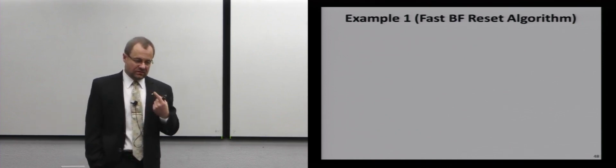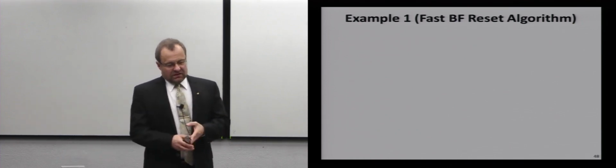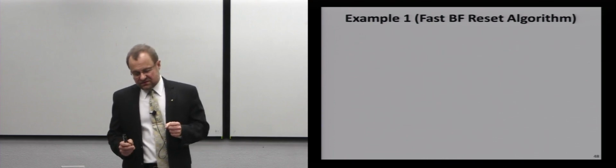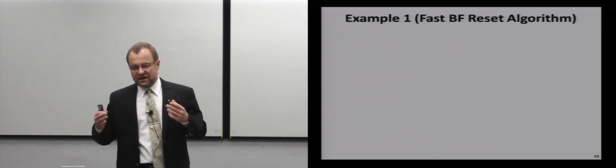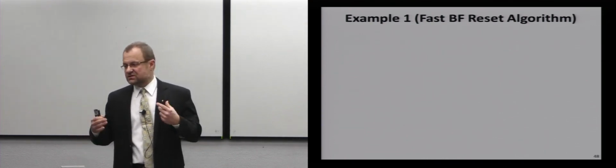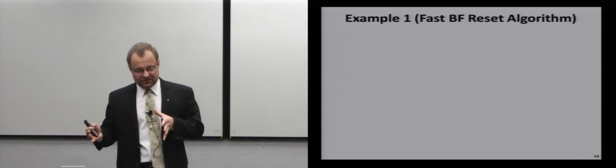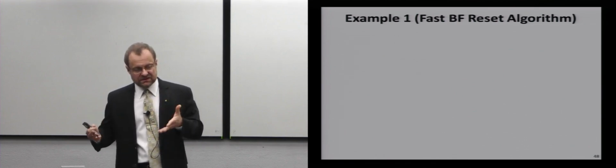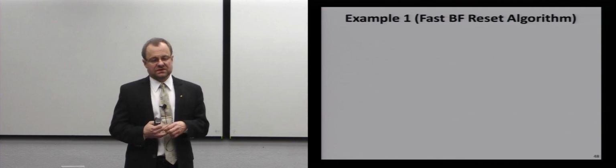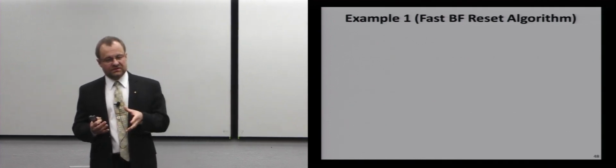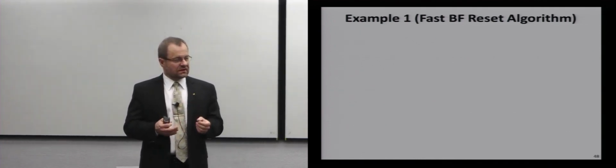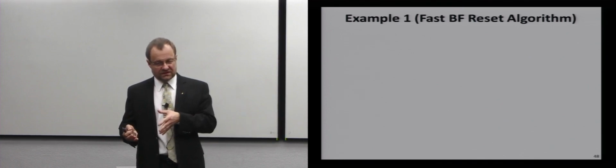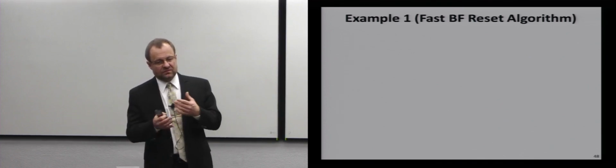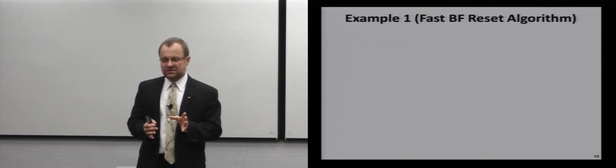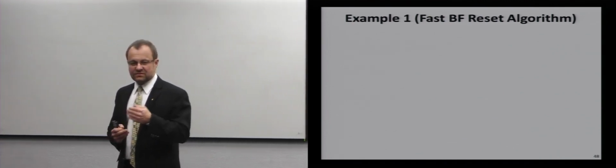Yeah. So what it is in high voltage systems, we duplicate relays, cabling, CTs, and so on, right? So you have to have two of them for availability. It also gives you this luxury that you could take one of the systems for maintenance, and there is the second one to protect your asset, and you don't have to shut down a transformer or a transmission line. So this is all good, except when it comes to a breaker.